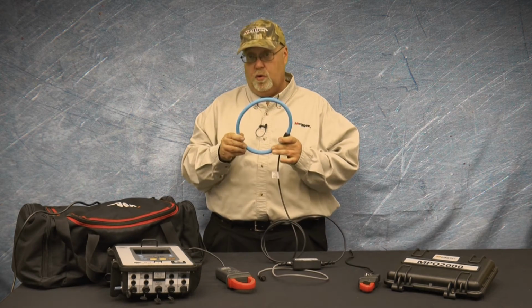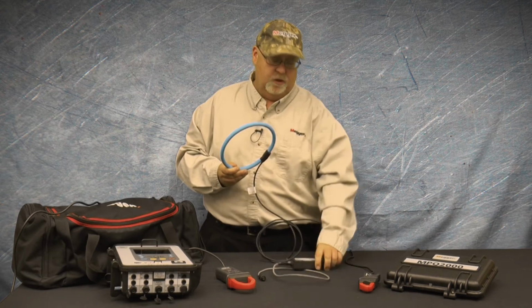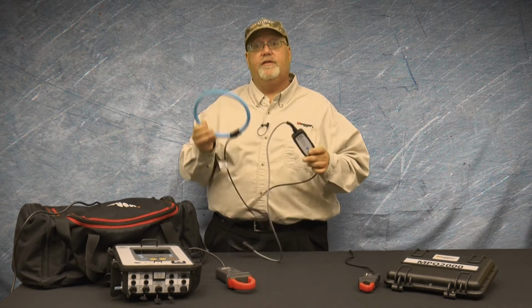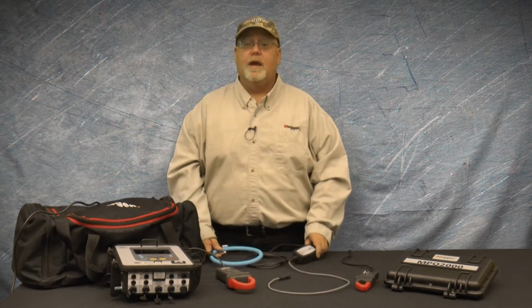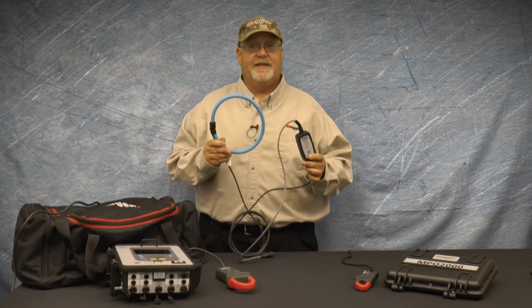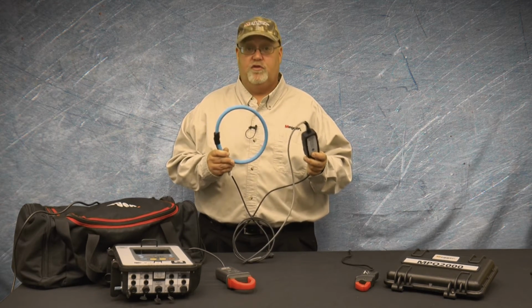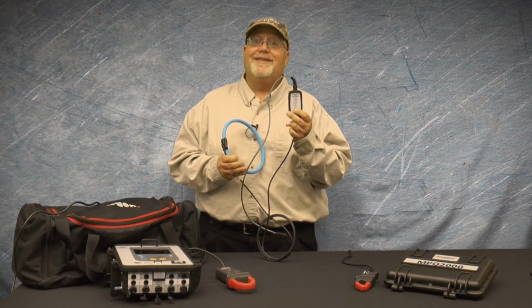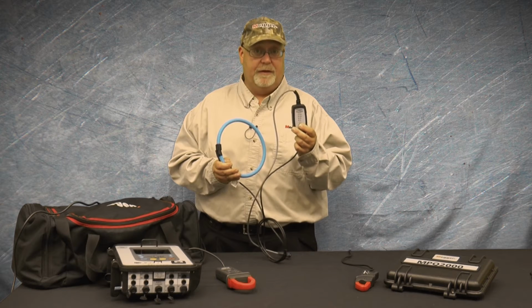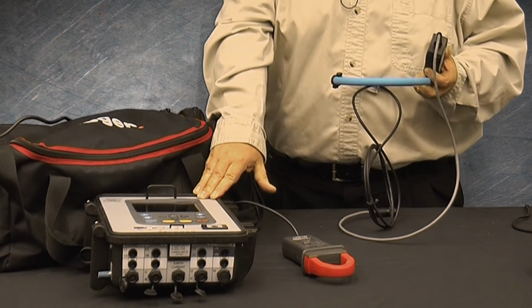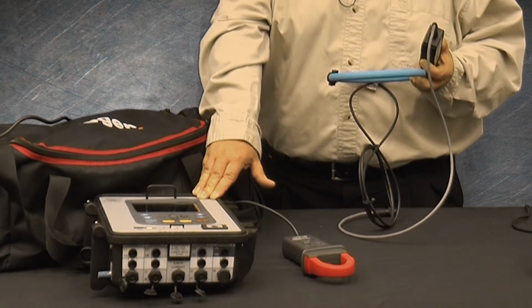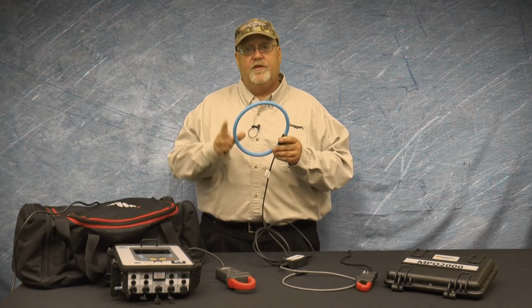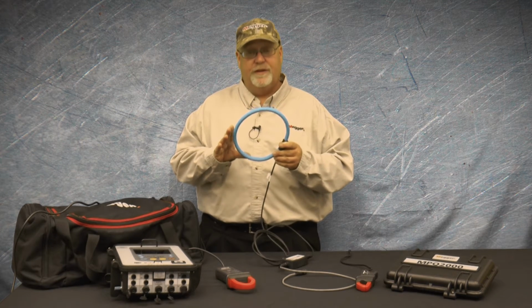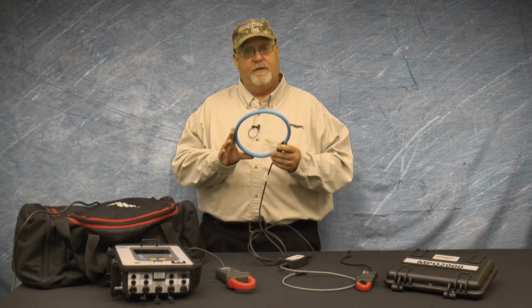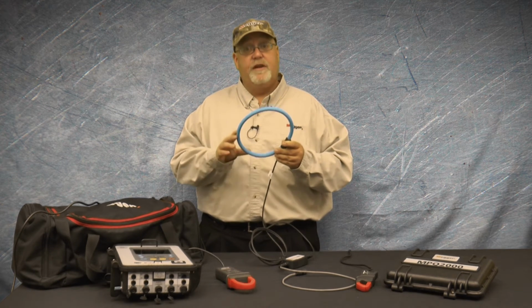Rogowski coils do not have iron cores that can saturate, so by alternating the gain stages, we can create CTs that have multiple ranges. The Megger line of MCCV6000 flexible current clamp come in 4 ranges. They support 60 amp, 600 amp, 3000 amp, and 6000 amp. And the Megger line of power quality analyzers will automatically identify what range the CT is in. Now, the advantage of having a current clamp that does not have an iron core is it cannot saturate. The disadvantage of having a CT that does not have an iron core is that you can have increased inaccuracies when measuring low levels of current.